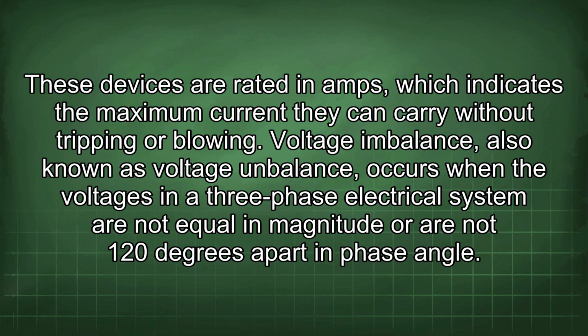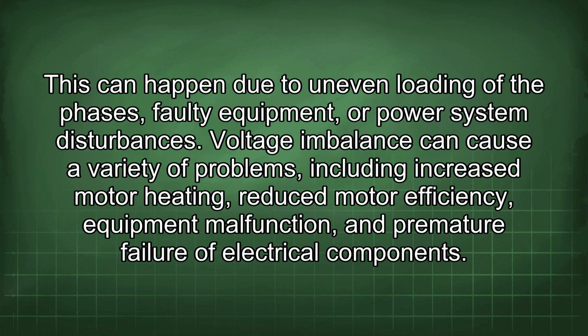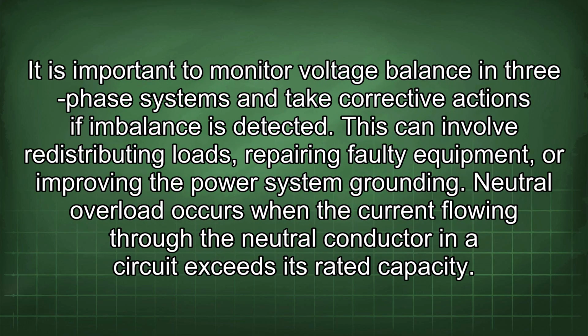Voltage imbalance occurs when the voltages in a three-phase electrical system are not equal in magnitude or are not 120 degrees apart in phase angle. This can happen due to uneven loading of the phases, faulty equipment, or power system disturbances. Voltage imbalance can cause a variety of problems, including increased motor heating, reduced motor efficiency, equipment malfunction, and premature failure of electrical components. It is important to monitor voltage balance in three-phase systems and take corrective actions if imbalance is detected. This can involve redistributing loads, repairing faulty equipment, or improving the power system grounding.